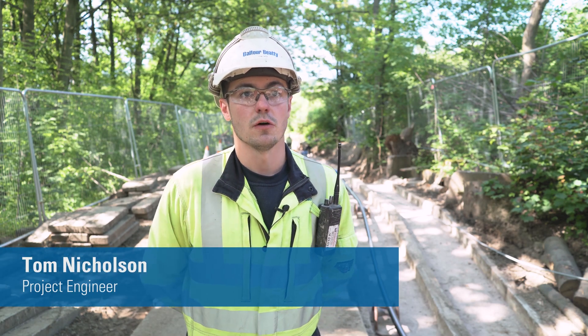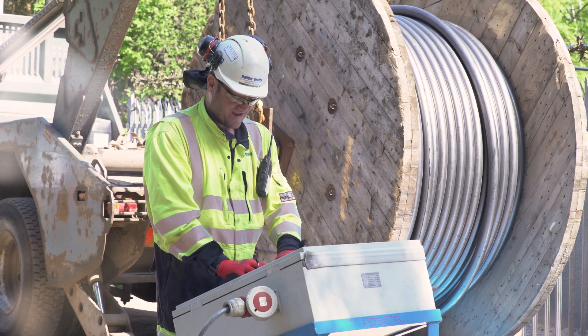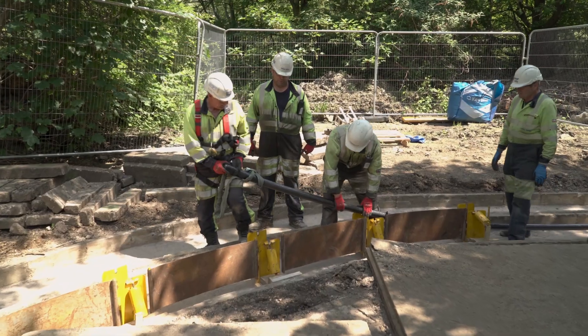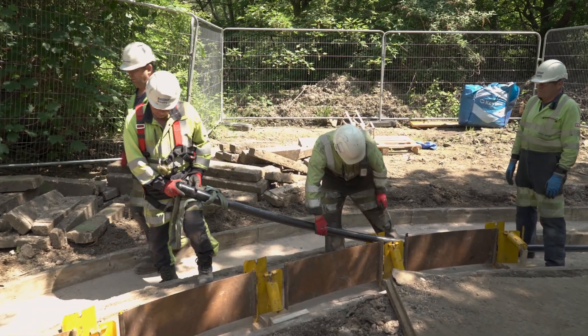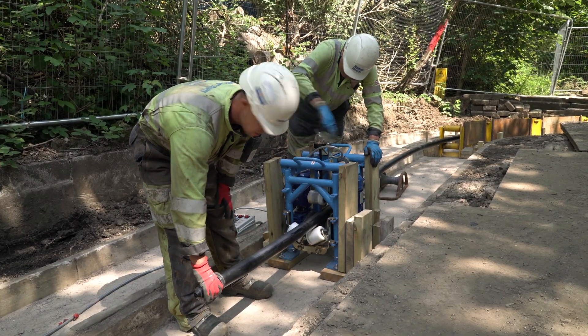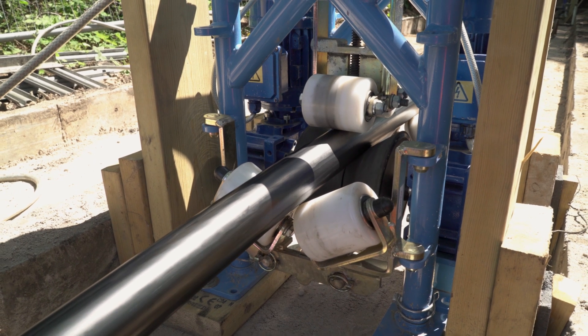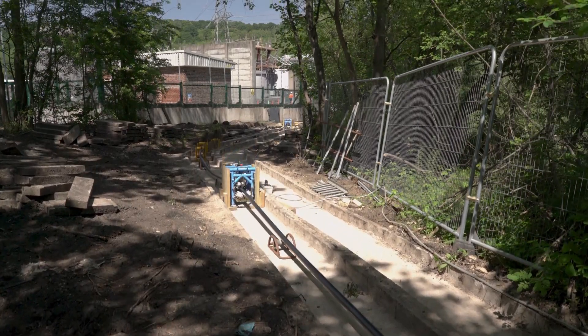We're working on behalf of National Grid and we're replacing the 33,000 volt cable at the end of its engineering lifespan. This method is a cable pusher method, so rather than using a winch and bond to pull the nose of the cable over rollers, we're actually pushing the cable through controlled motorized pushes. These are placed at intervals along the cable route.